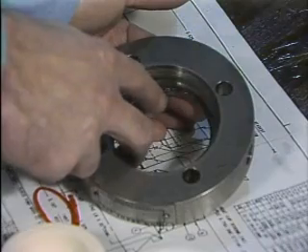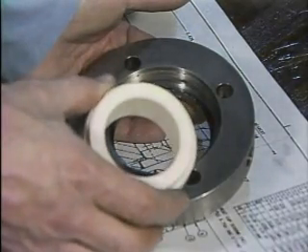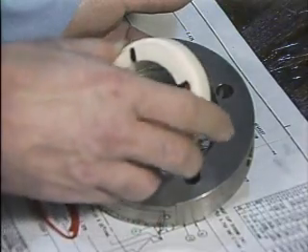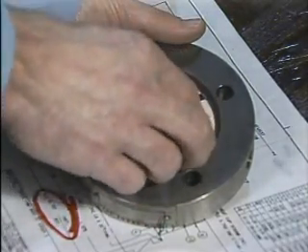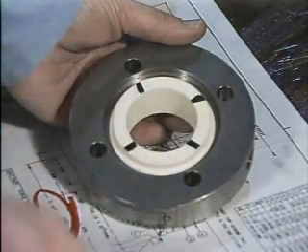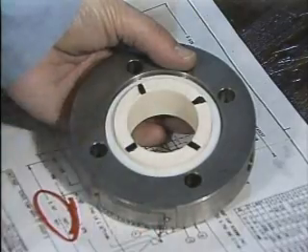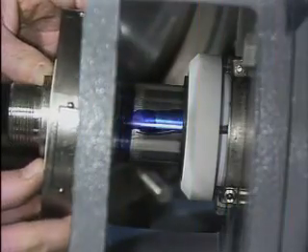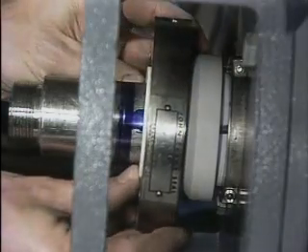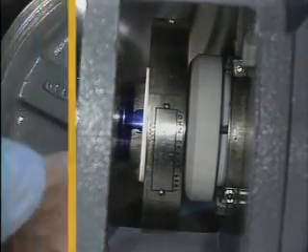A gasket is placed in the gland plate. Then the mating ring is installed. On an outside seal, the polished side of the mating ring is installed so that it faces away from the stuffing box. Then a second gasket is installed, and the gland plate assembly is ready to be mounted onto the shaft. The gland plate should be slid back on the shaft as far as possible and positioned against the rotating element that was just installed.